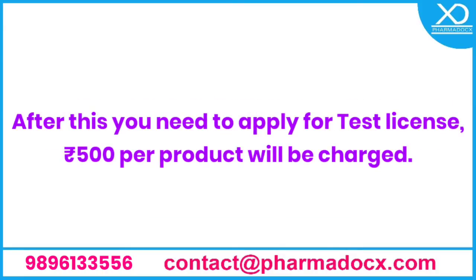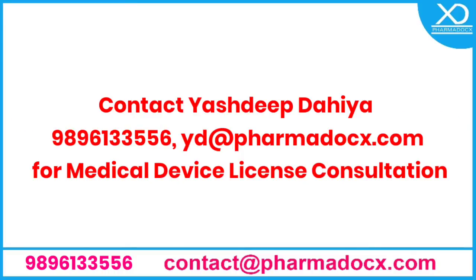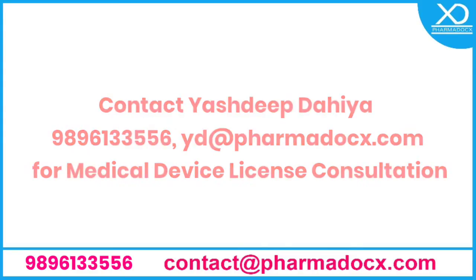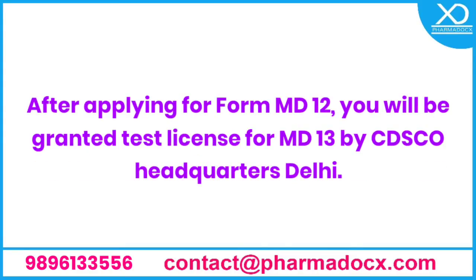After getting the user ID and password, you need to apply for a test license. This is done on the CDSCO portal and rupees 500 per product fees is charged. After applying for the test license on Form MD12, you will get a test license on MD13 from CDSCO headquarter Delhi.